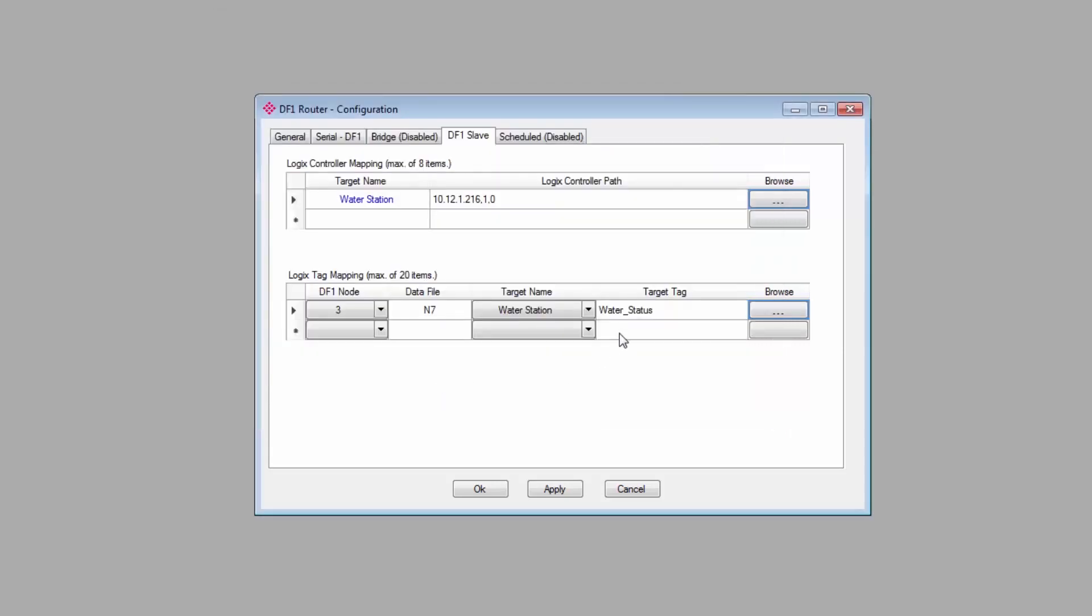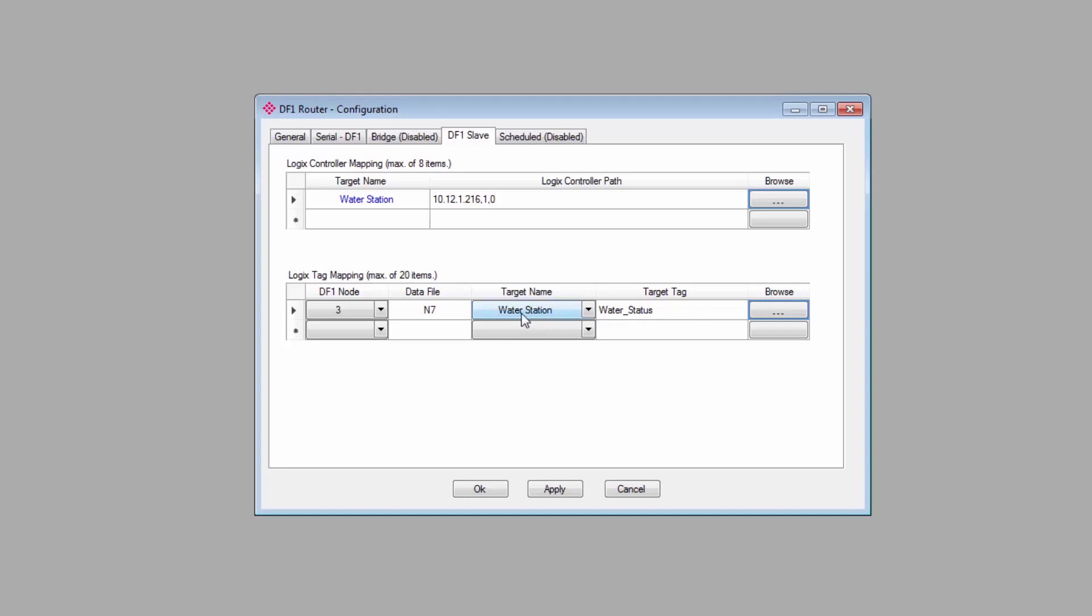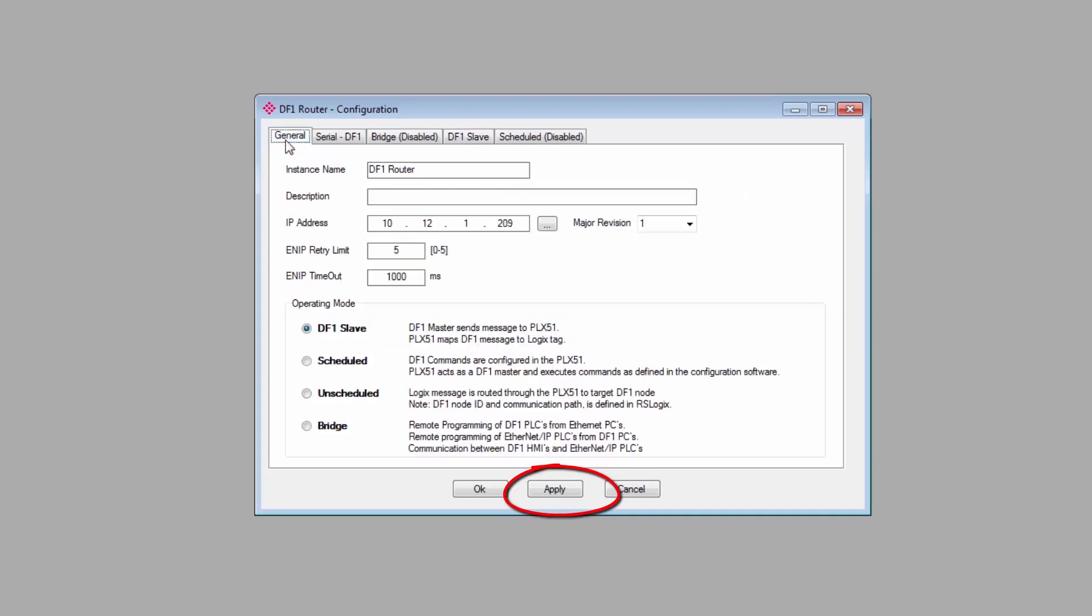So now, if a request comes in from the master on the DF1 network for node 3, and it wants to read data file N7, the data will come from the Water Status tag in the Water Station controller at this location. And that should do it. We'll click the Apply button, and now the configuration should be ready to download to the gateway.